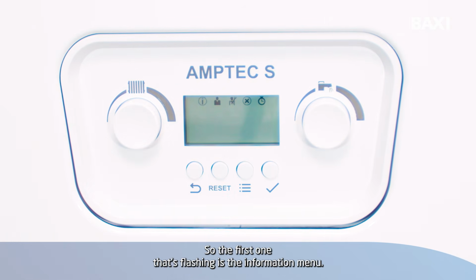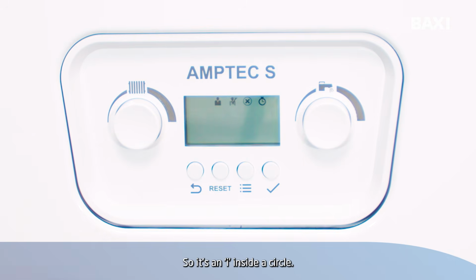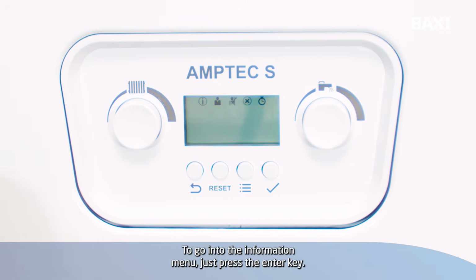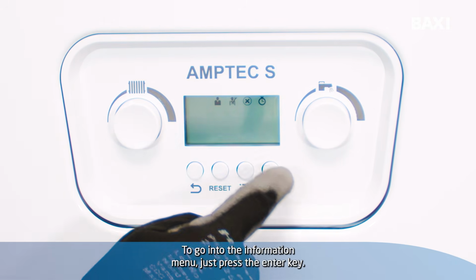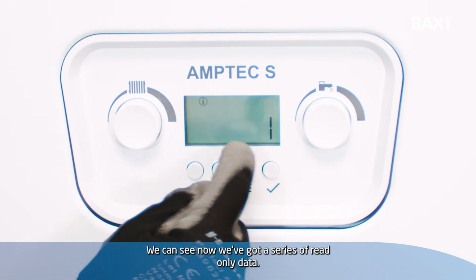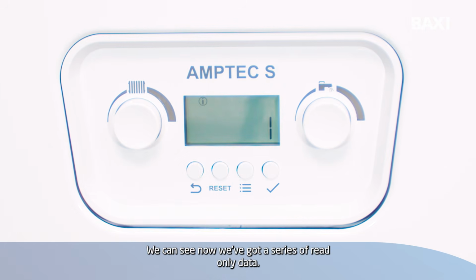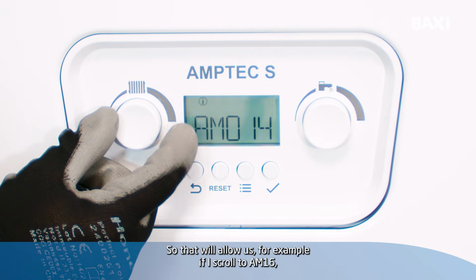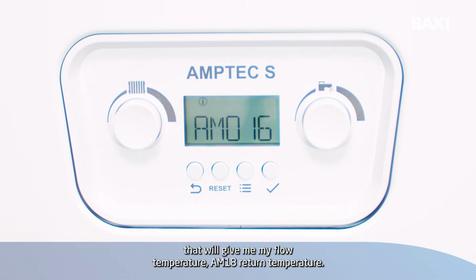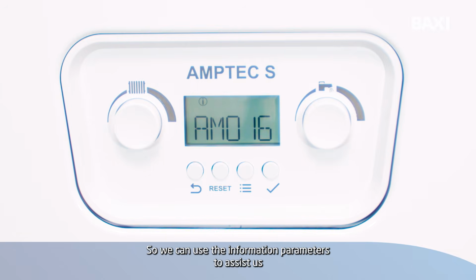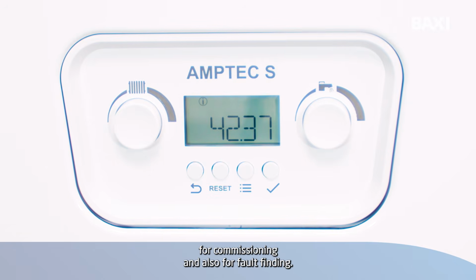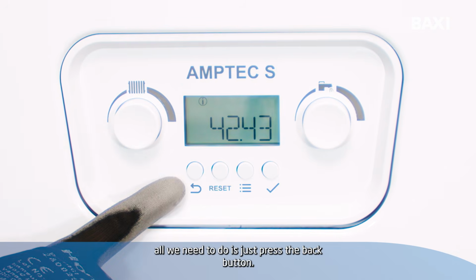So the first one that's flashing is the information menu. So it's an eye inside a circle. To go into the information menu, just press the enter key. And we can see now we've got a series of read-only data. So that will allow us, for example, if I scroll to AM 16, that will give me my flow temperature, AM 18, return temperature. So we can use the information parameters to assist us for commissioning and also for fault finding. Now to come out of the information menu, all we need to do is just press the back button.